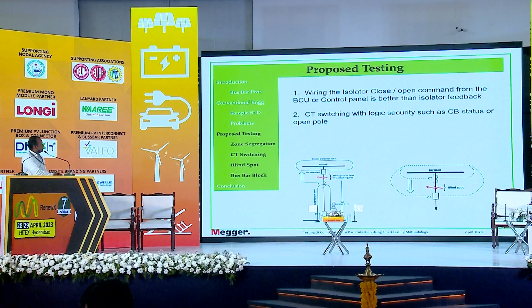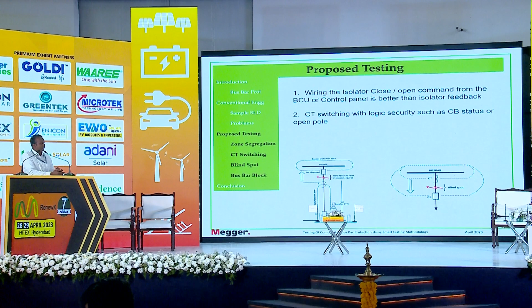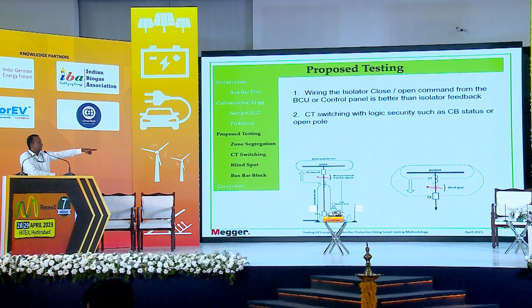So this is called an end fault system. We have two types of operation which are very popular in Europe and UAE countries, that is, where the CT is located. So the bus bar, circuit breaker, then the CT. In this case, the bus bar, CT and the breaker. In both these cases, if there is a fault between the CT and the breaker, the entire tripping logic would be different. The entire logic has to change because this is an in-zone fault and that is an out-zone fault.